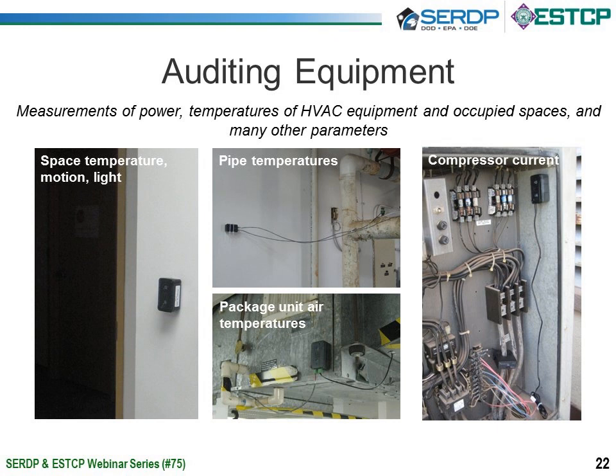So for the auditing, we're looking at many different things. On the left here, this is an example of a sensor just placed into an office space. So we're looking at space temperatures, humidity, light levels, and motion in these buildings to understand how well the existing control system and HVAC systems are performing, and look for various energy savings opportunities. There's also a lot of sensors placed on the HVAC equipment. So for instance, pipe temperatures, measuring the chilled water, hot water supply and returns to get an understanding of how well the equipment is performing itself, as well as a lot of sensors into air handlers and package units, looking at the airstream temperatures.